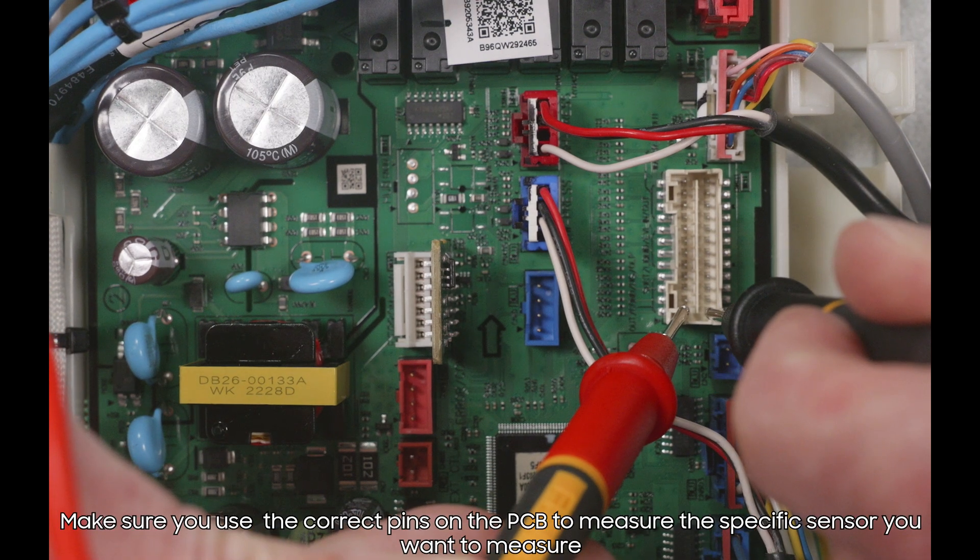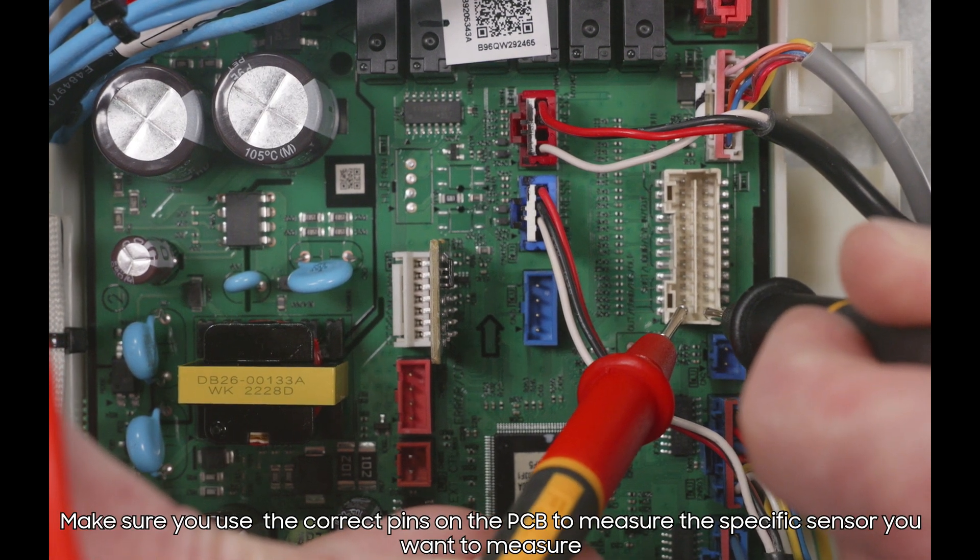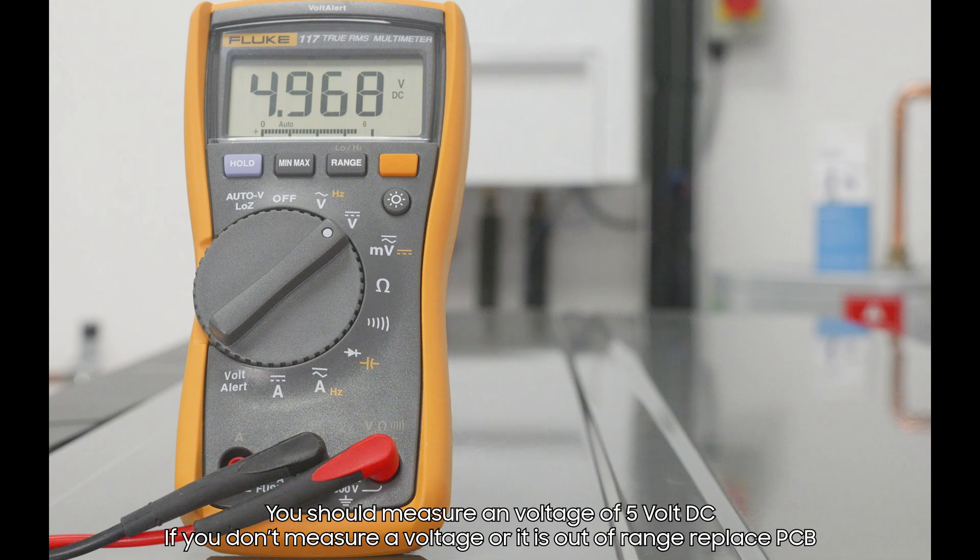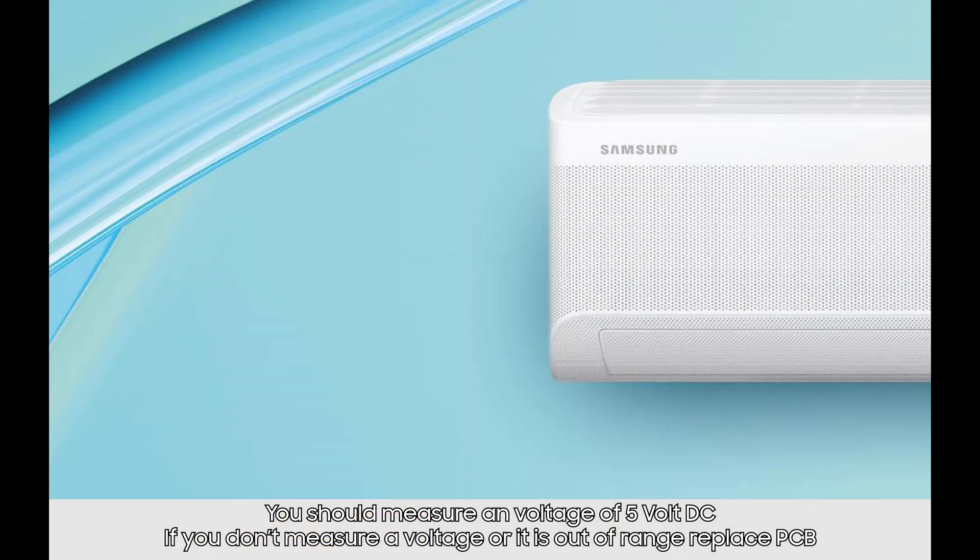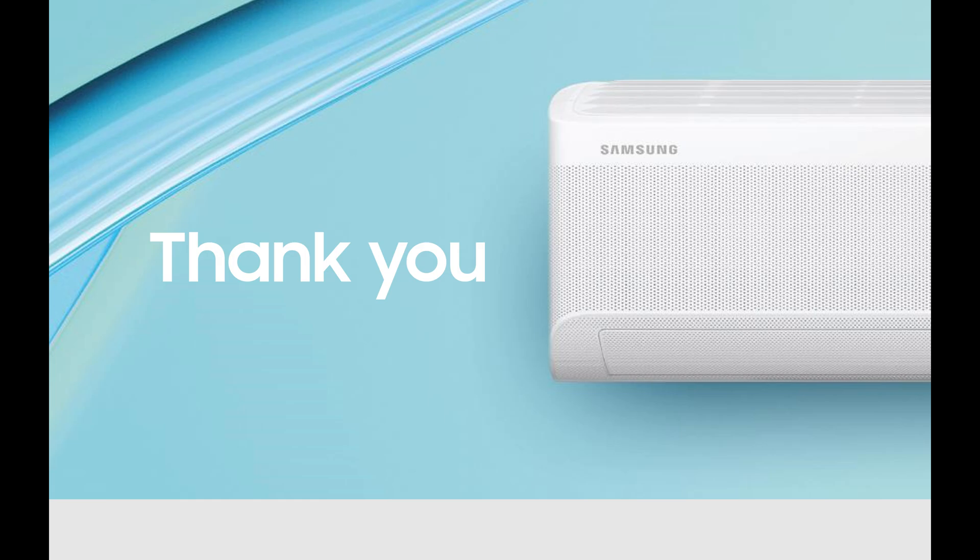Make sure you use the correct pins on the PCB to measure the specific sensor you want to measure. You should measure a voltage of 5 volts DC. If you don't measure voltage or a value out of range, replace the PCB.